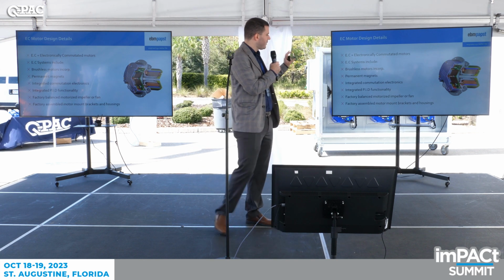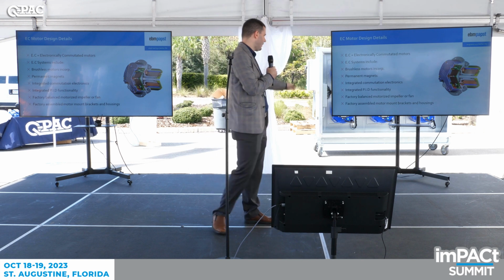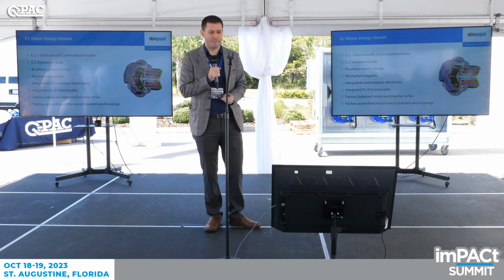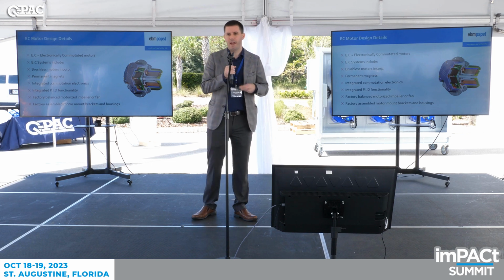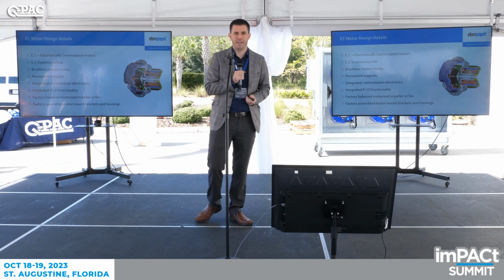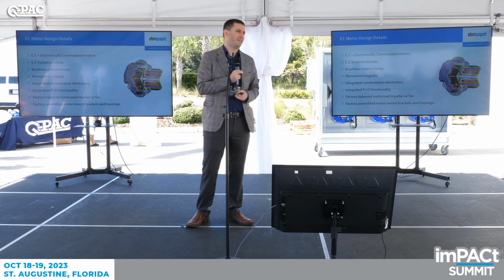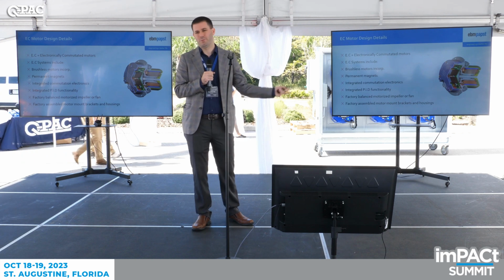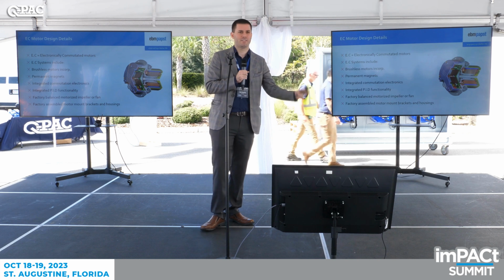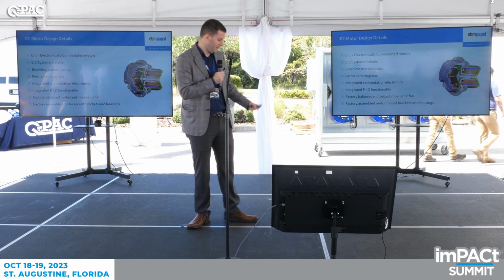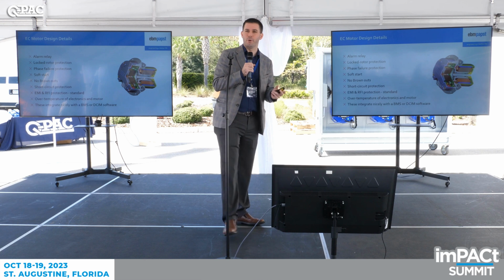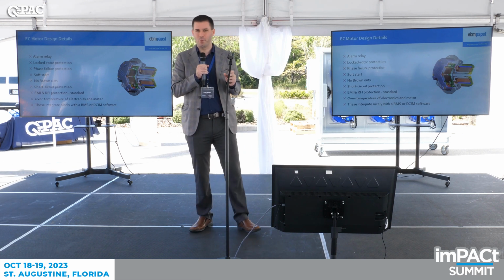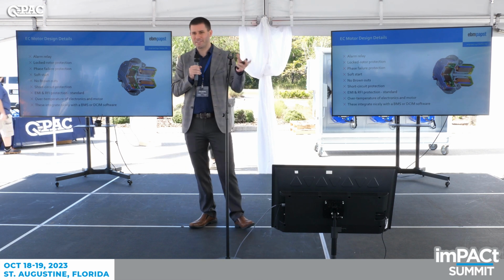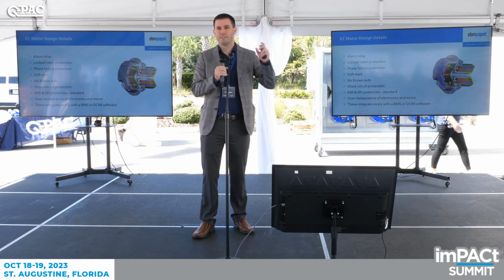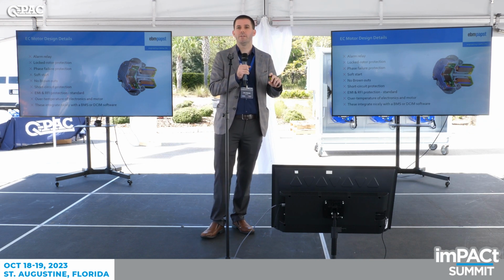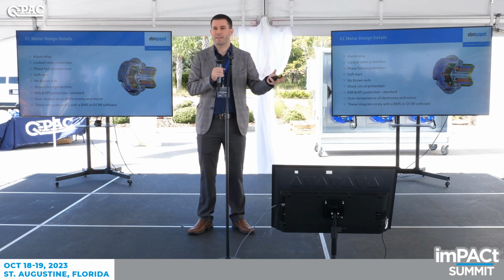It has the integrated commutation electronics and PID functionality. Everything's factory balanced before it gets sent to you. Every single motor gets factory balanced and factory tested, so there's no way to get a fan dead on arrival or anything. It runs through a whole bunch of tests on all the wiring contacts, does 100% speed, 40% speed, and has an alarm relay built in. It has locked rotor protection. What it actually does when the rotor's locked on our fan is sense that the rotor's locked and try to start, send out the alarm that, hey, I can't start, it's locked, and then wait 3 seconds and try again.